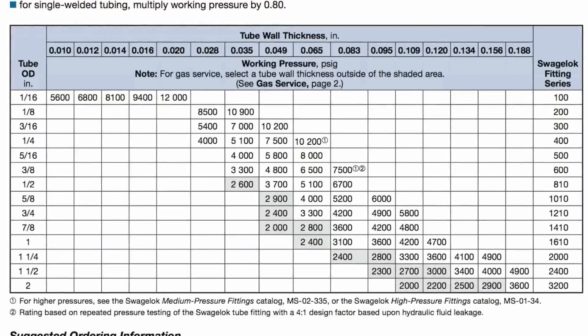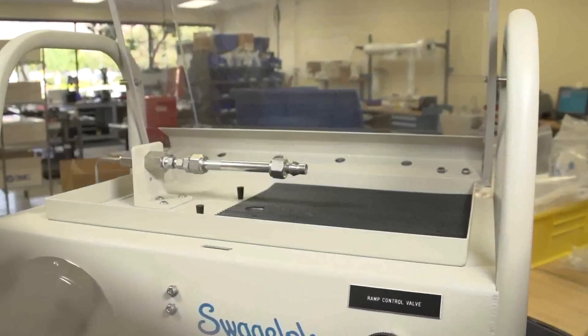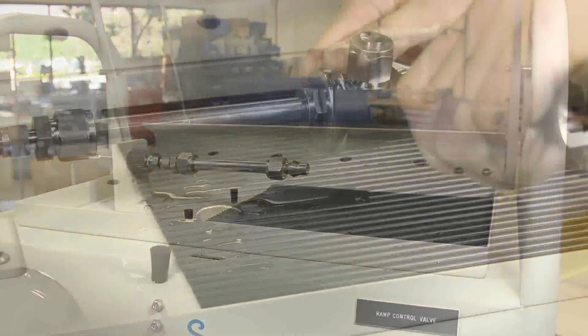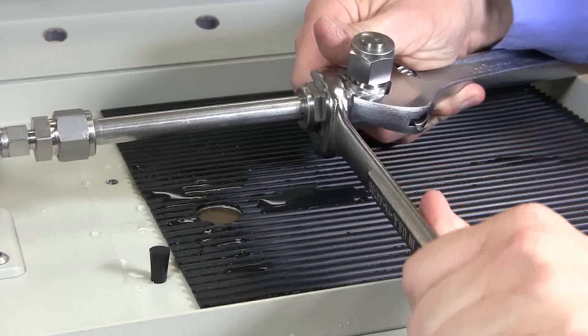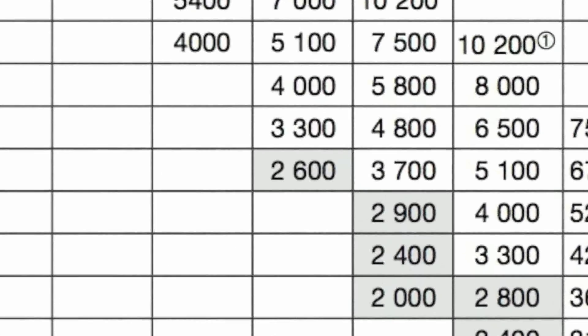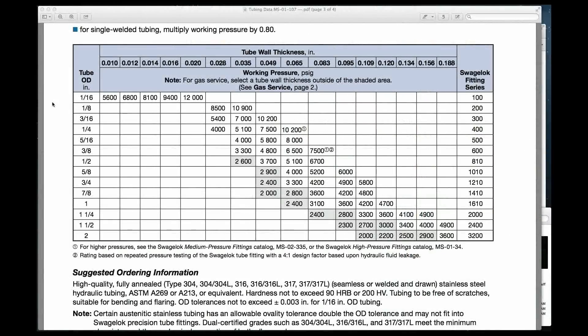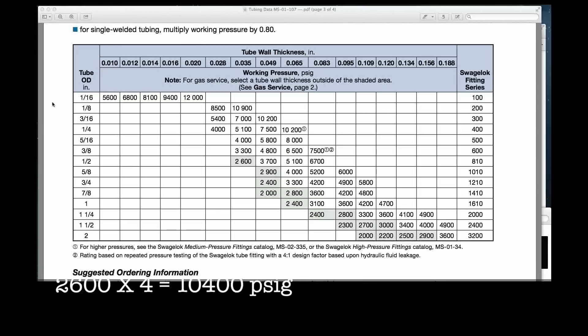Working pressure ratings that are shaded are for liquid service, not gas service. We will be bursting 316 stainless steel seamless tubing. The OD is half inch and the wall thickness is 0.035 inches. According to the tubing data table, it has a suggested allowable working pressure of 2600 PSIG in liquid service. Using the typical tubing safety design factor of 4 to 1, its estimated minimum burst pressure is 10,400 PSIG. Now that you know that important information, you are ready to guess — when will it burst?